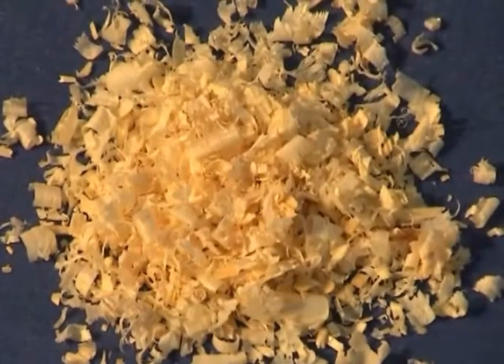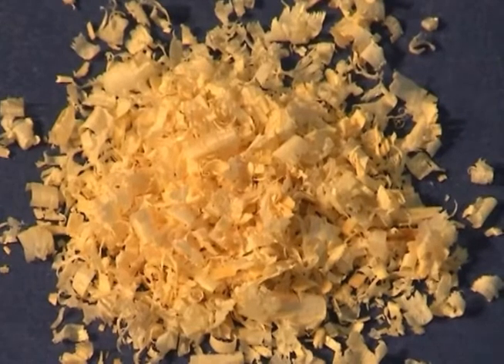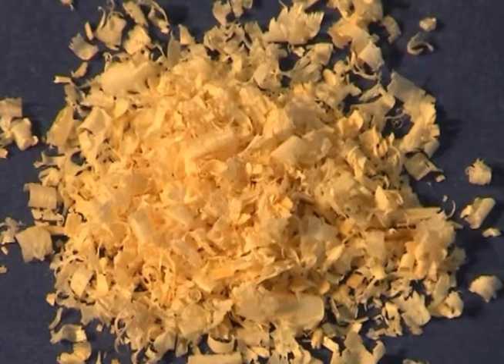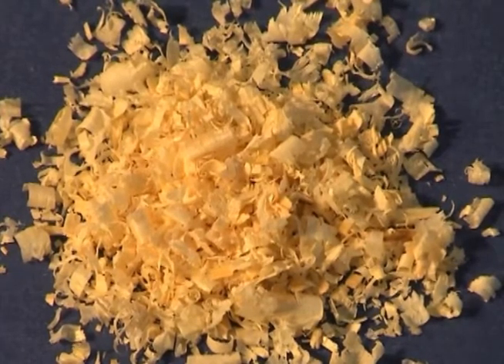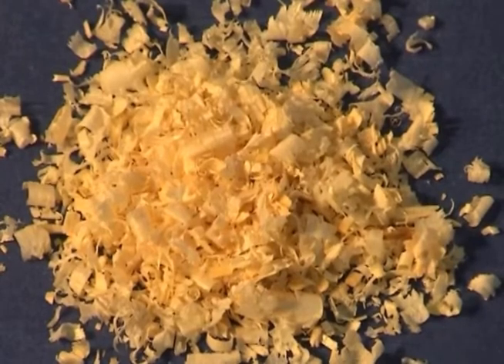These chips are larger than 0.5 mm and the fraction of dust below 0.5 mm is minor, so this dust is not explosive. Fall speed is typically above 100 cm per second.